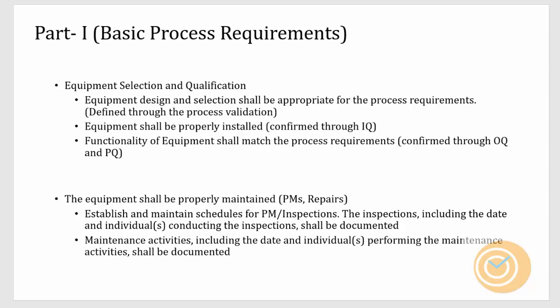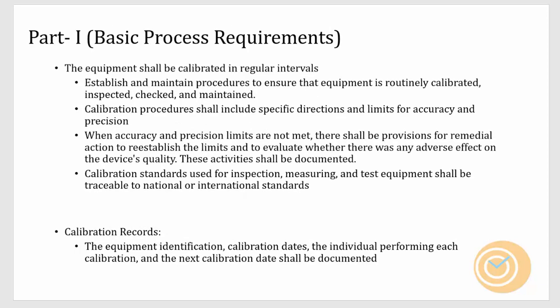When preventative maintenance is done, you need to have proper schedules, and you have to make sure that the date and the individuals who are conducting the inspections or the preventative maintenance are recorded. Same thing when you are doing any maintenance activities: the date and individual performing the maintenance activities shall be documented. And the calibration requirements. The equipment should also be properly calibrated at regular intervals. You have to have schedules so that the equipment is calibrated.